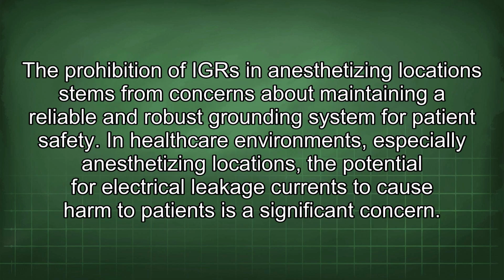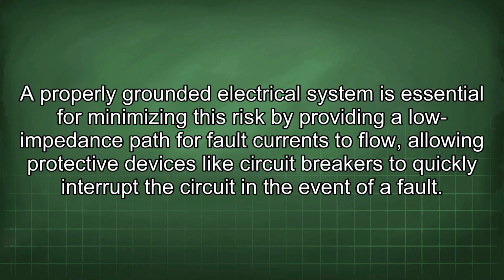The prohibition of IGR in anesthetizing locations stems from concerns about maintaining a reliable and robust grounding system for patient safety. In healthcare environments, especially anesthetizing locations, the potential for electrical leakage currents to cause harm to patients is a significant concern. A properly grounded electrical system is essential for minimizing this risk by providing a low impedance path for fault currents to flow, allowing protective devices like circuit breakers to quickly interrupt the circuit in the event of a fault.